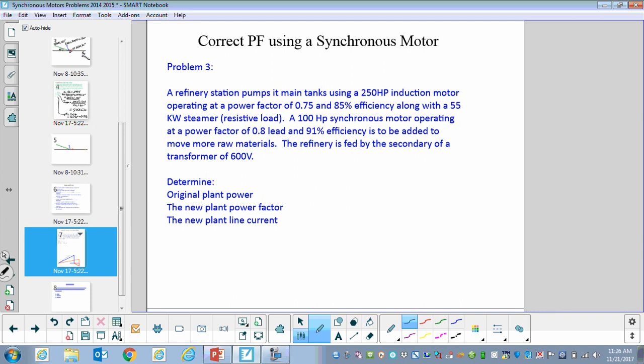So we have a refinery station that pumps its main tanks using a 250 horsepower induction motor, operating at a power factor of 0.75 - that's actually pretty good - and 85% efficient, along with a 55 kilowatt steamer, so there's a resistive load there. A 100 horsepower synchronous motor operating at a power factor of 0.8 lead and 91% efficient is to be added to move more raw materials. The refinery is fed by the secondary of a transformer of 600 volts. It says determine original plant power, the new plant power factor, and the new plant line current.